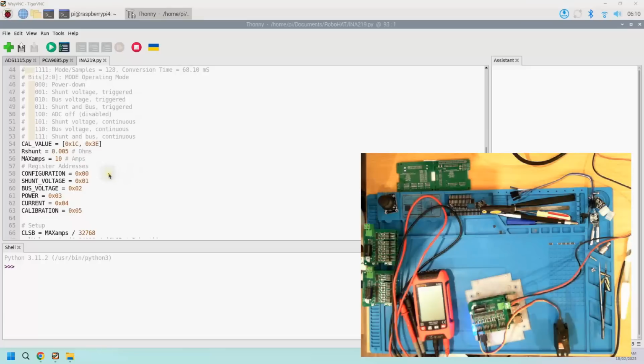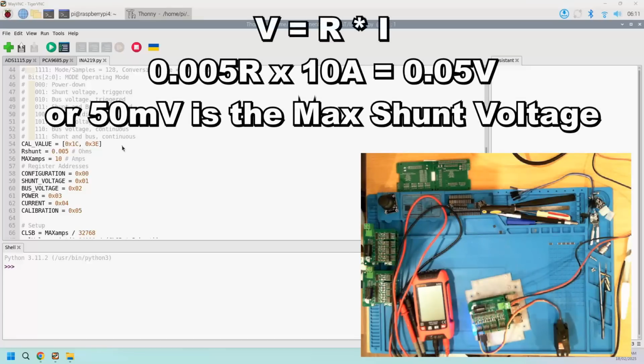Alright, so registers, cal value. Cal value is something that I will come back to. It's a calibration value, and then we've got R shunt and max amps. Now max amps is the maximum number of amps that we are expecting to see through the shunt resistor. And if you know the value of your shunt resistor, which is R shunt, and in this case it's 0.005 ohms, then you can calculate the microvolts or volts that you're going to see across that shunt at 10 amps. So in this case, you'd be looking at 50 millivolts or thereabouts.